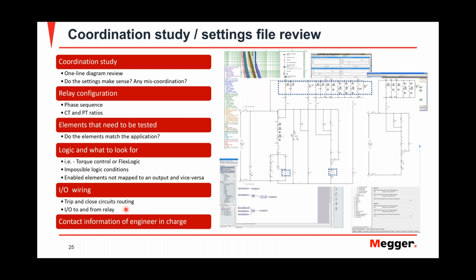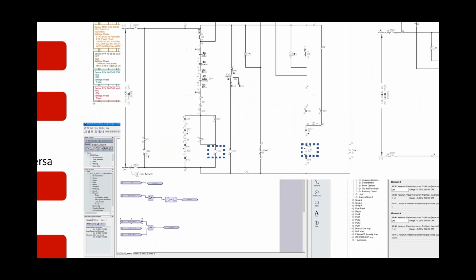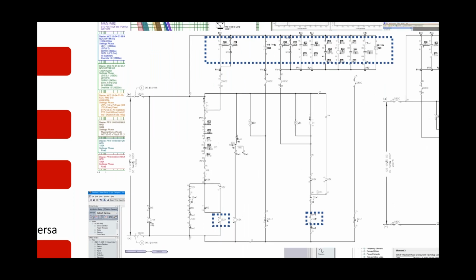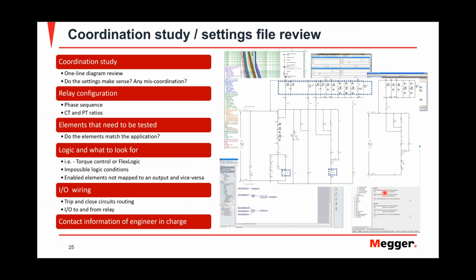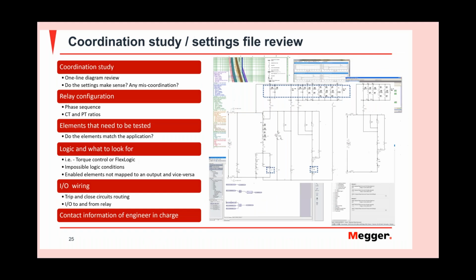When you look at the wiring, know where the IO is on the relay, and if they're mapped correctly to, let's say, in this case, you're looking at a closing coil and a tripping coil and a breaker, knowing that that particular output is mapped and it's the closing coil for the breaker. The same thing for your tripping coil, for your trip logic. All that stuff you should have. You could do a review before you show up on the site. And at the end, make sure that you have the contact information of the engineer in charge if you have any questions. So that's something that you should have.